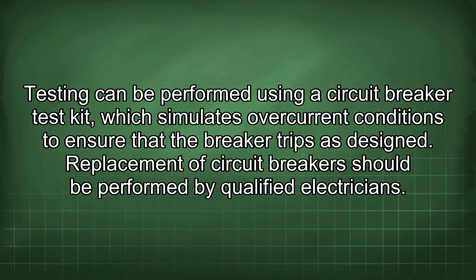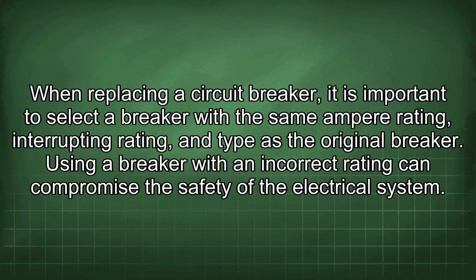Replacement of circuit breakers should be performed by qualified electricians. When replacing a circuit breaker, it is important to select a breaker with the same ampere rating, interrupting rating, and type as the original breaker. Using a breaker with an incorrect rating can compromise the safety of the electrical system.